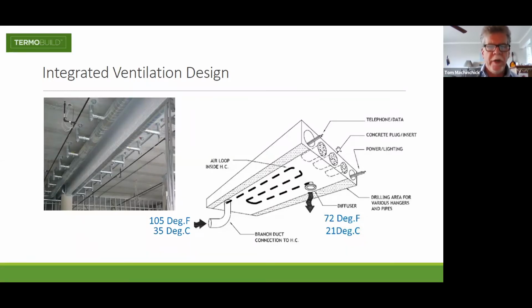So what an integrated ventilation design does is it takes a standard hollow core slab and modifies it to actually make it part of the ventilation system. So you have an input duct coming into the concrete slab where a hole is drilled. The air travels through the raceways that are made here and exits into the room or the building through a standard diffuser. The temperature of the air, whether it's hotter in the summer or cooler in the winter, comes through the concrete hollow core slab and is conditioned before it enters the room. On the left, you see an actual picture. This duct here is the main or one of the main HVAC ducts. And you can see these small L joints that are connecting to the concrete slab to form the duct in the slab itself.